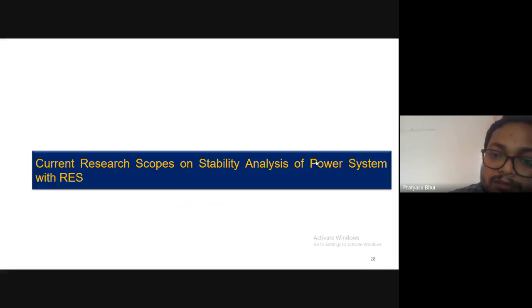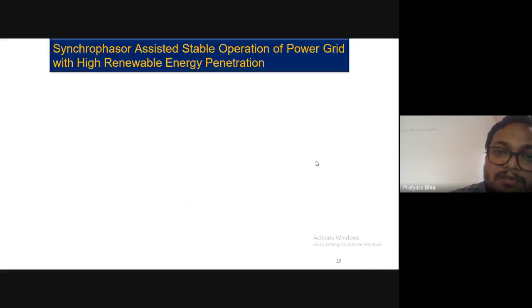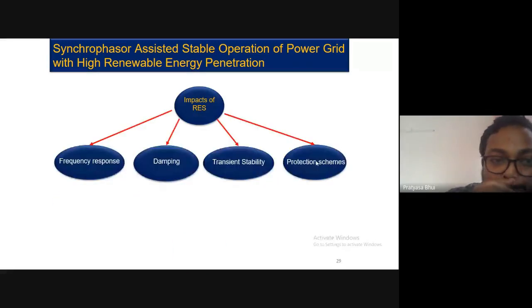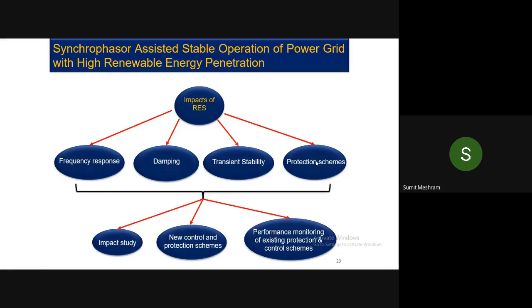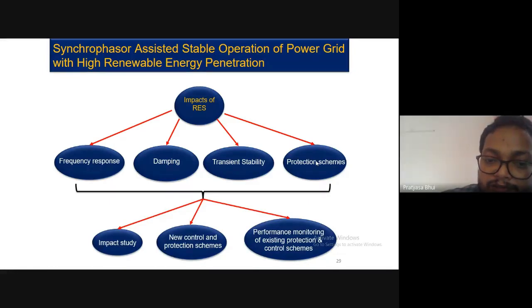If we focus only on the stability analysis of power systems with renewables, then you have frequency response, damping, transient stability, and protection schemes, and the impact of IBRs. So in all these areas, you have to first see what the impacts will be. If there is any detrimental impact, then you have to design some new control and protection schemes. But not all the existing controllers and protection schemes will be scrapped. So there will be some existing protection and control schemes, and the question is how to monitor the performance of those protection and control schemes.